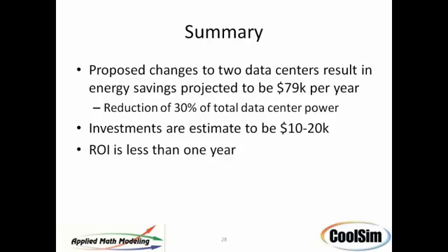In this case, we didn't spend a lot of money. We used curtains. They're flexible curtains, made of effectively plastic. They're fused at the top. They drop in the case of fire. They're not hard surface at all. They're soft. They're quite effective. They're very cost efficient. I estimated that to do those 2 data centers with those curtains, $10,000 to $20,000 at the most. Projected savings here, $80,000 a year from doing what we recommended.